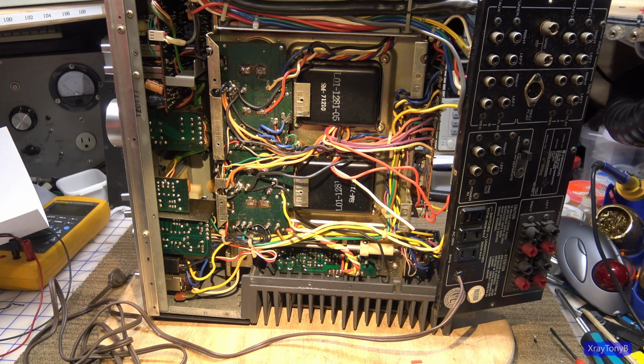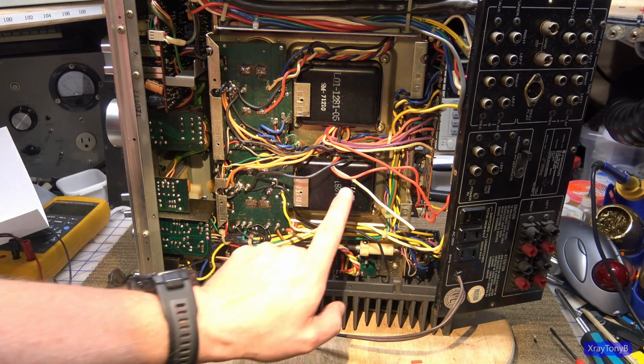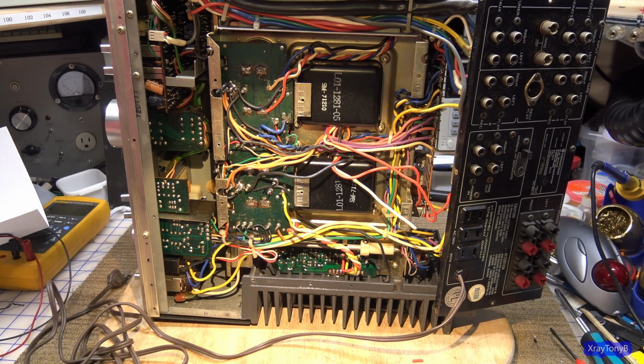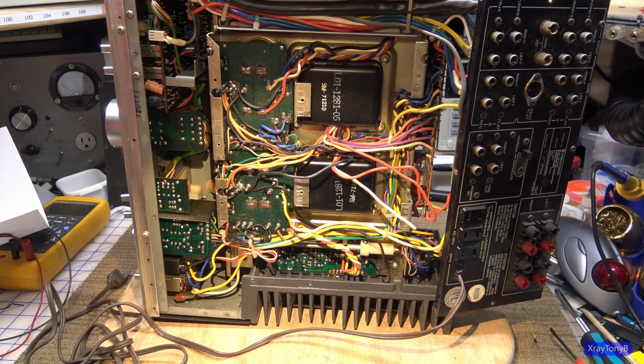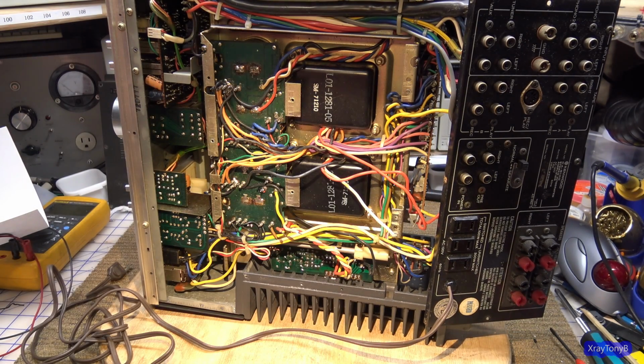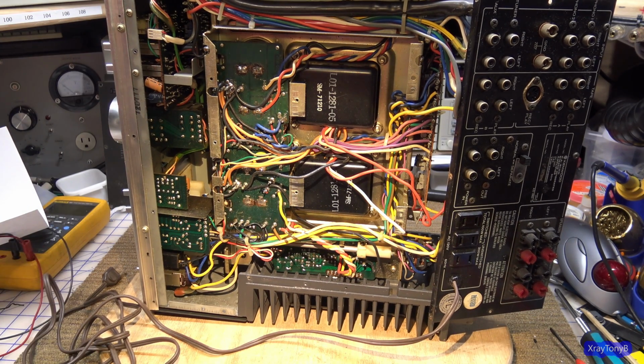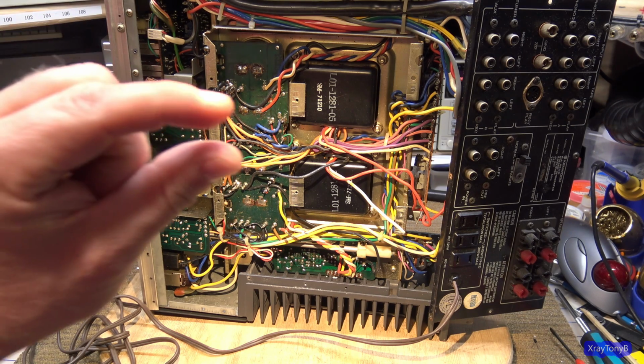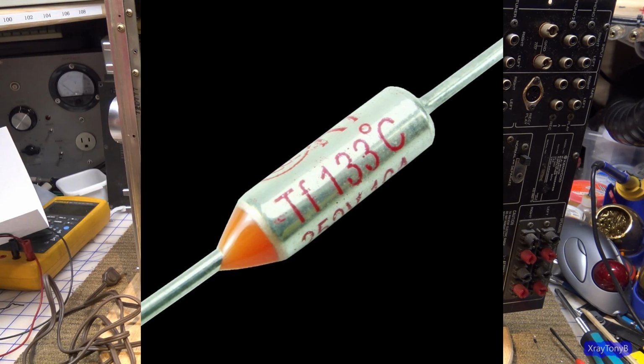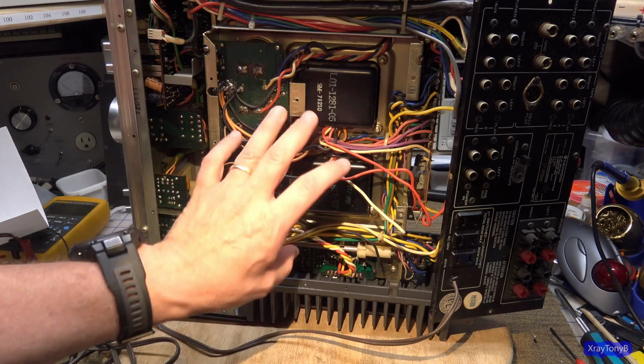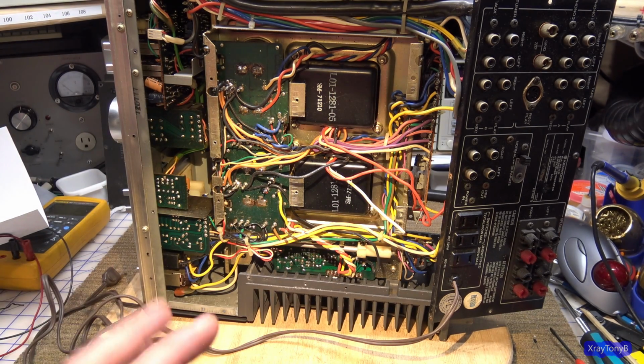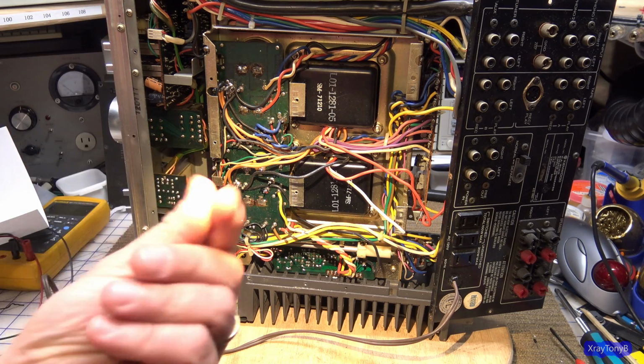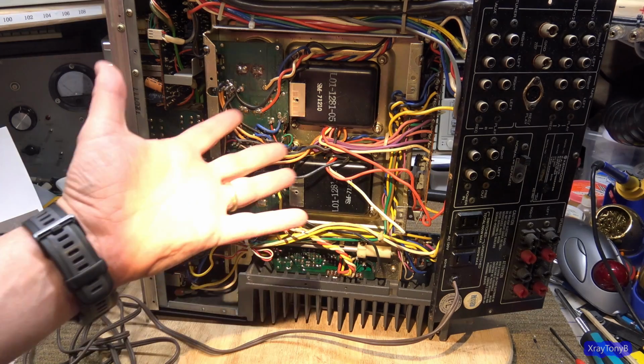First thing I want to do is thank a whole bunch of you who gave me a little tip on this that I didn't know. And that is, these transformers actually have a thermal fuse inside of them. Now, I really never thought about these smaller ones having that in them, but apparently they do. Now, a thermal fuse is just a small device. It's not very big, a little square thing with two little wires, and they usually put it inside. It can be buried inside the windings, or it can be right underneath the final tape wrap inside the transformer. And the whole point of it is, if the transformer overheats, that heat will cause the fuse to open up, which will protect the transformer windings.